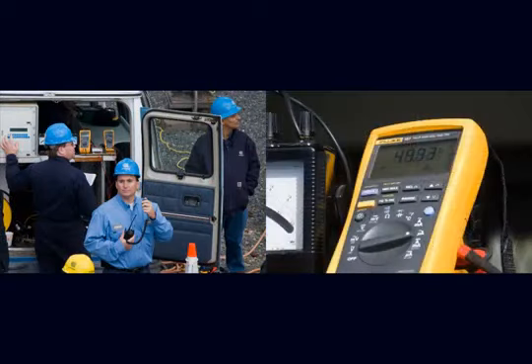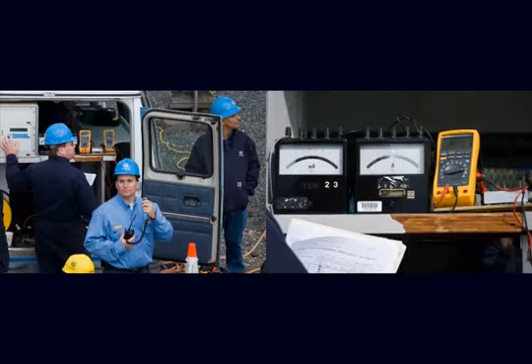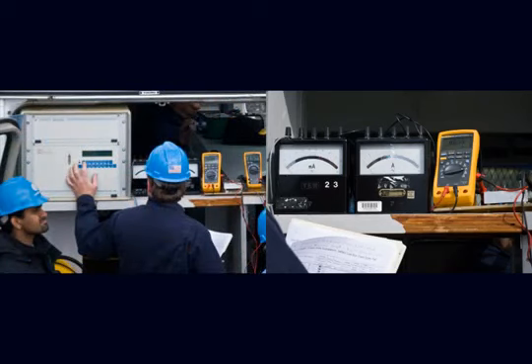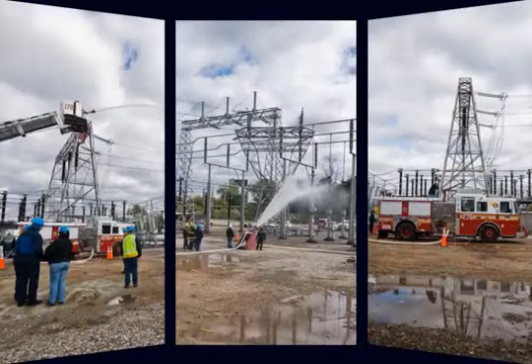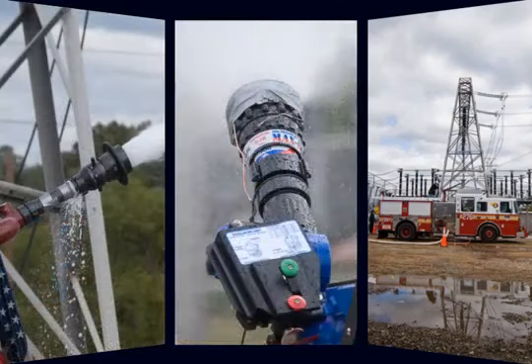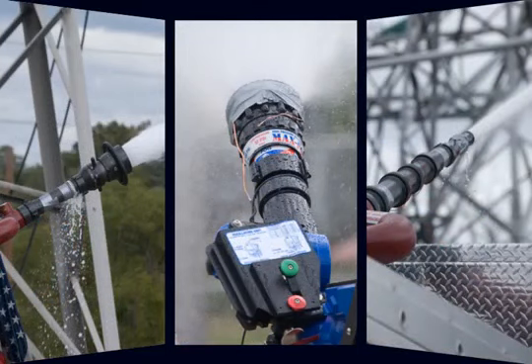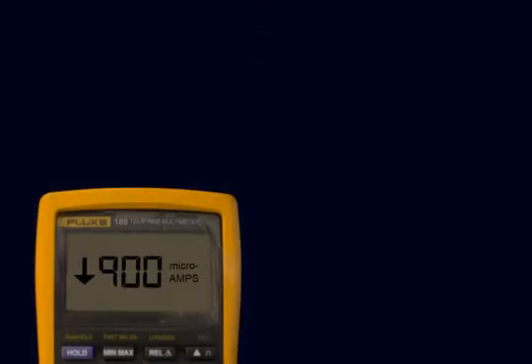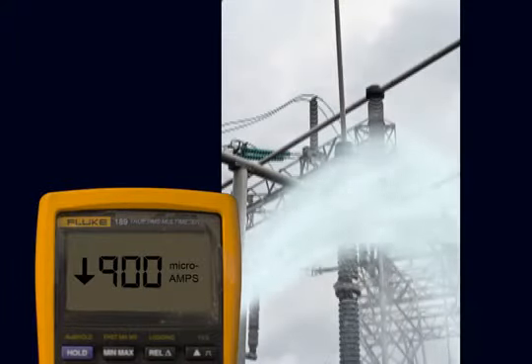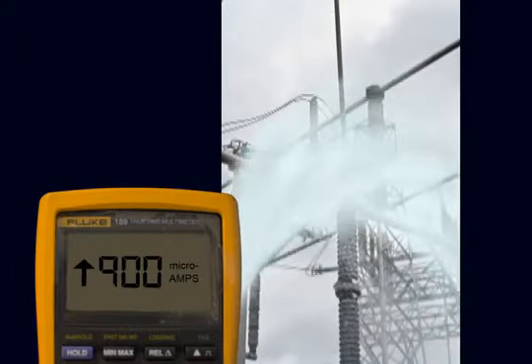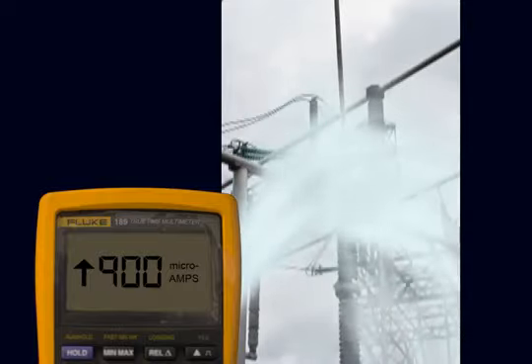It was measured by a digital ammeter and 2 analog meters. A digital fault recorder was also installed to record the electrical waveforms, so later on we could go back and look at the exact data on a computer. The testing philosophy required us to look at a variety of ways the foam could be delivered by the fire department in order to prove each method safe. The safety target for leakage current is 0.9 milliamps or below. 0.9 milliamps is the level at which leakage would cause a physiological effect, basically an electrical shock as we know it.